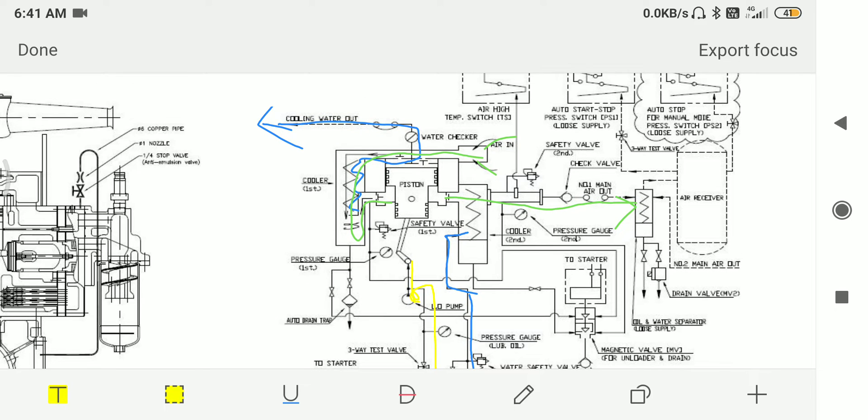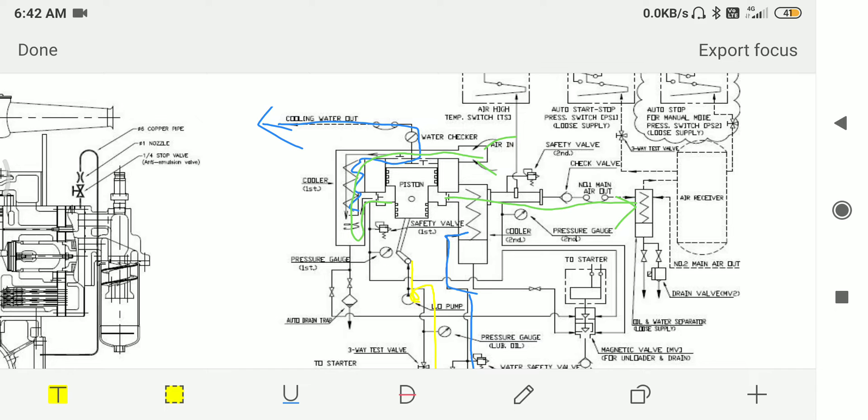The green line represents the air flow. The air takes suction from the filter and goes to the first stage compression, then goes to intercooler, from intercooler to the second stage, from second stage to the aftercooler, from aftercooler to the oil separator, and then to the main air receiver.